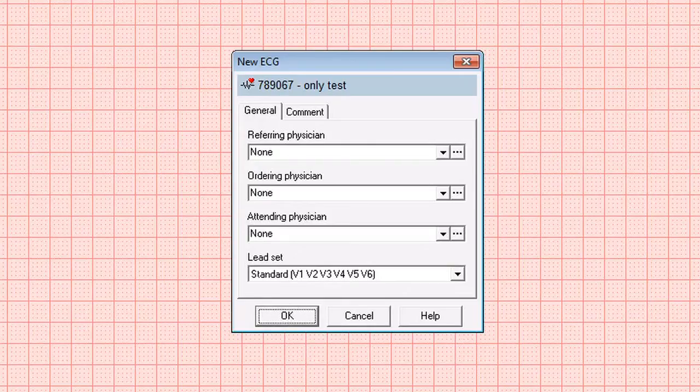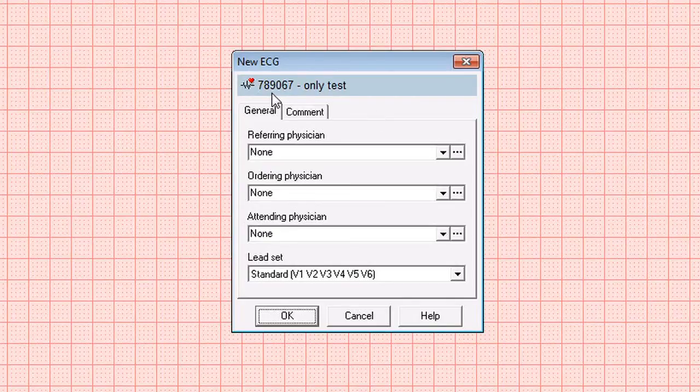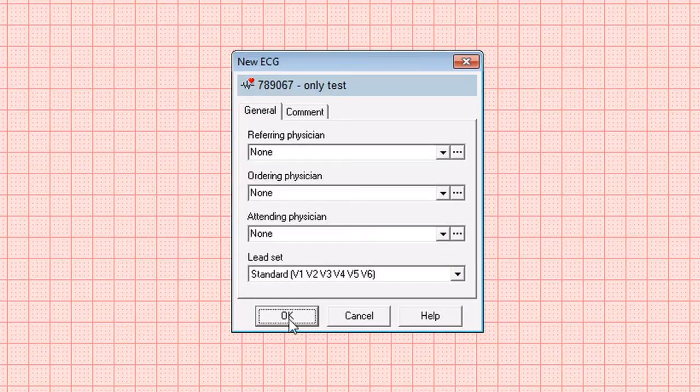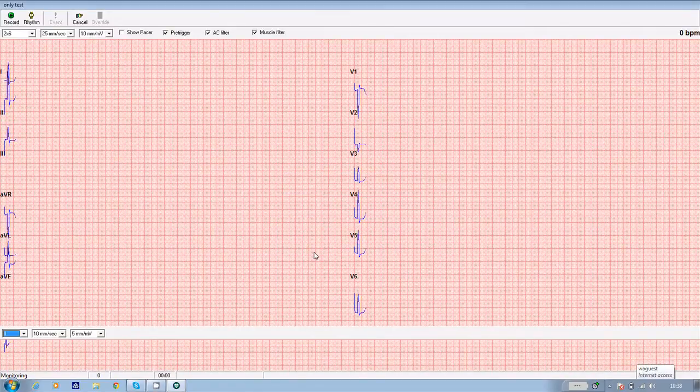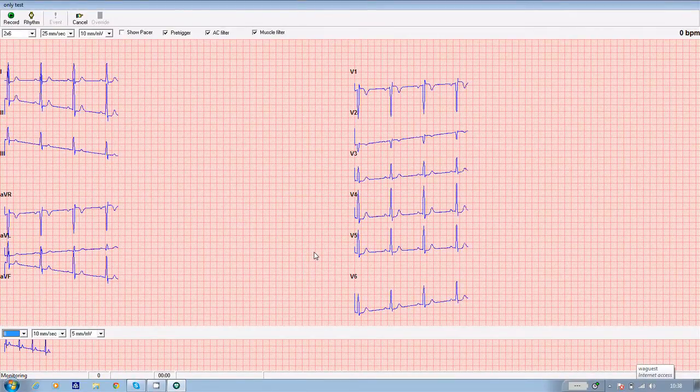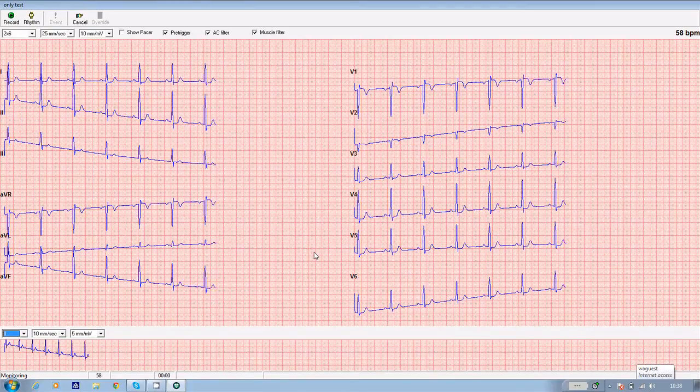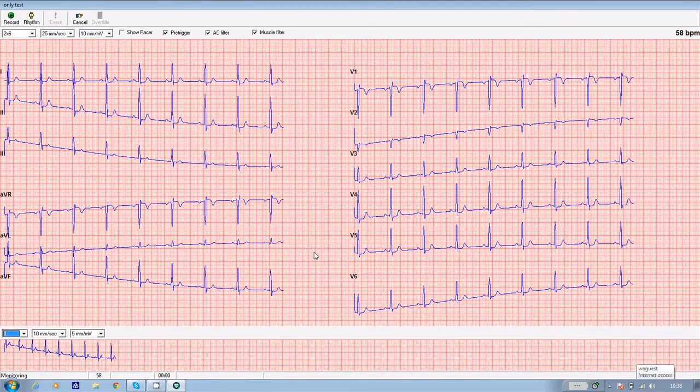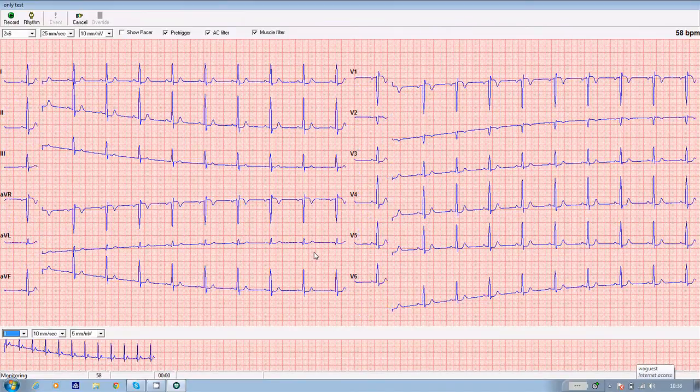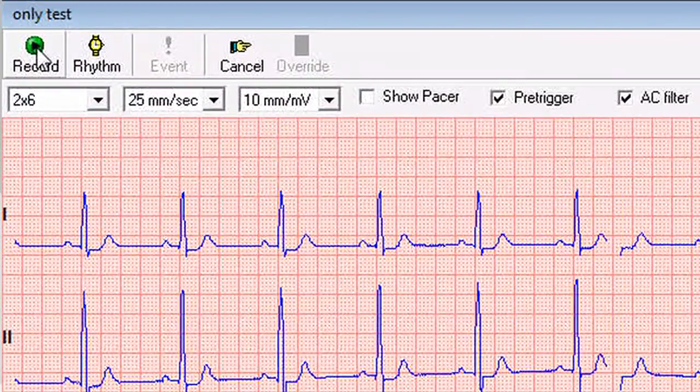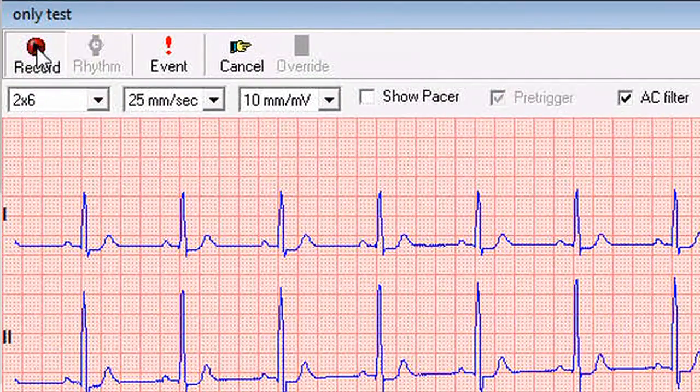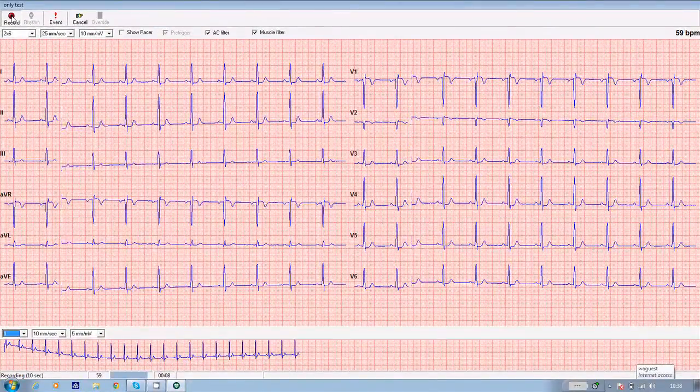The software then loads the module. You get a box up on screen which says new ECG, confirms the number and the name of the patient, and all you need to do to take the ECG is to click OK. The traces will then appear on screen in real time. Now you can wait until these have settled down and stabilized and you're getting a good trace test from each of the patient's leads. And when you're happy with that, you click on record in the top left hand corner of the screen. And from that point, the software records 10 seconds of ECG.